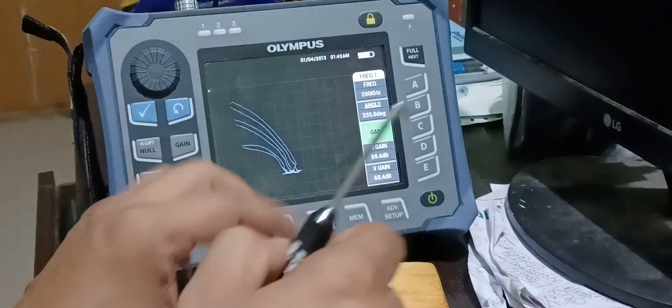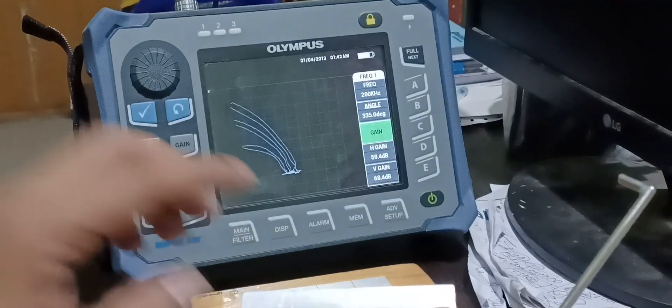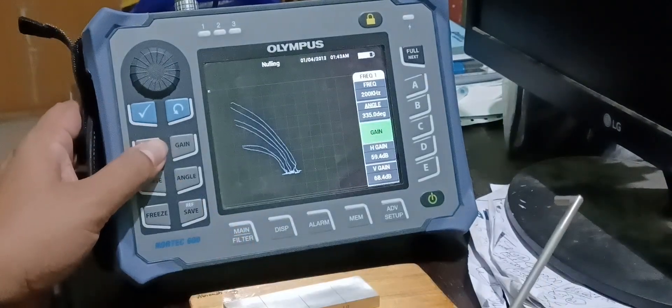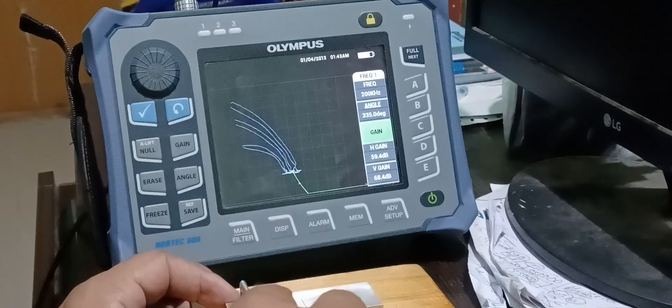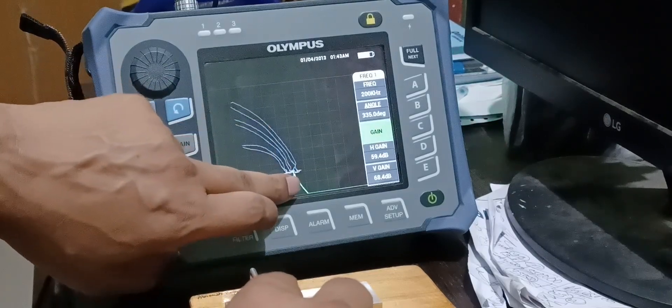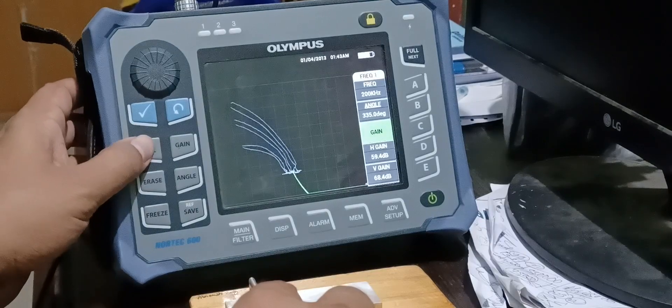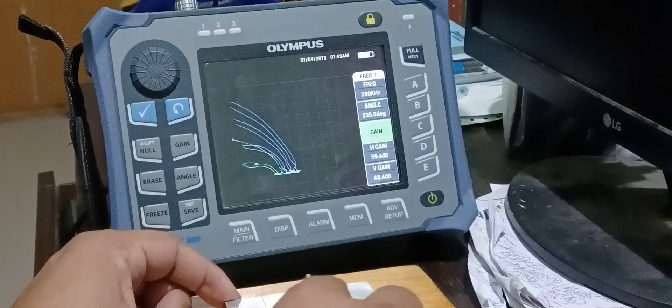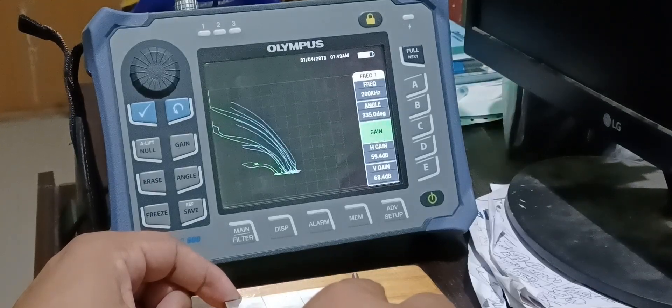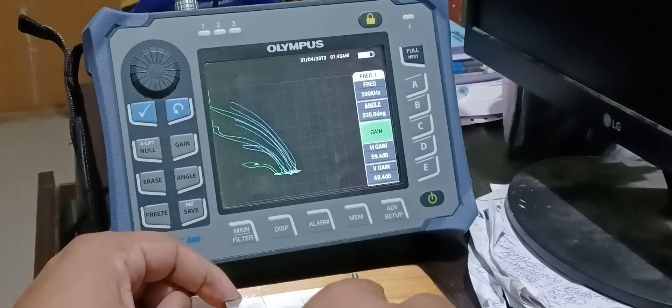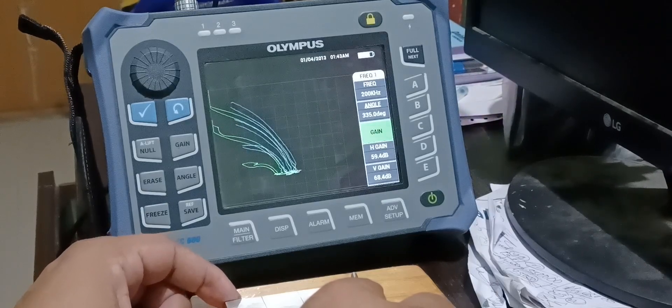Now, what we will do? I will try to catch up by comparing the depth, by comparing the crack signal from this standard. So, what we will have to do? I will press the null button again. Now, it is coming to this bottom center. I am putting the probe, putting the part over here. Now see, everything is now appearing in a green line. Now, these are my reference signal, and these are my current signal. I will again null it here. Now, I will try to catch, find these three cracks, first crack, second crack, and third crack. You can see how clearly these three cracks are identified with respect to the earlier set reference graph.